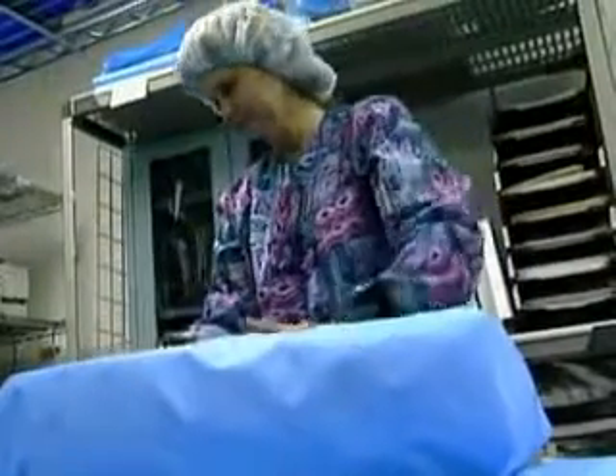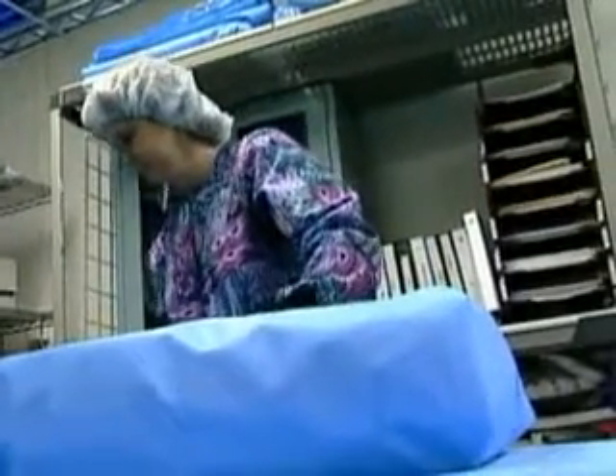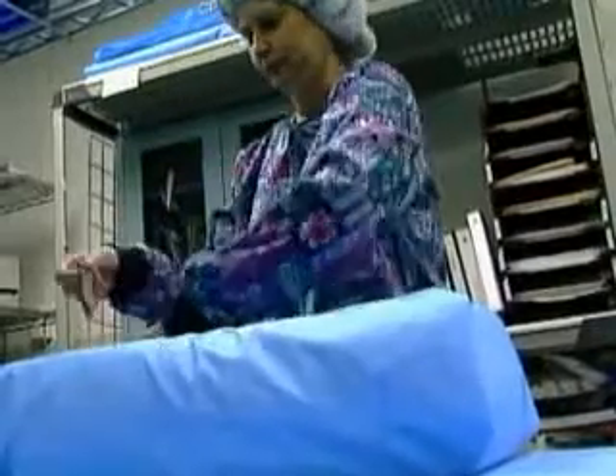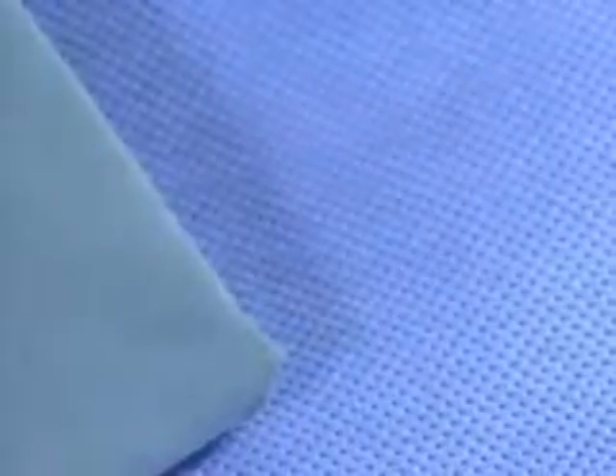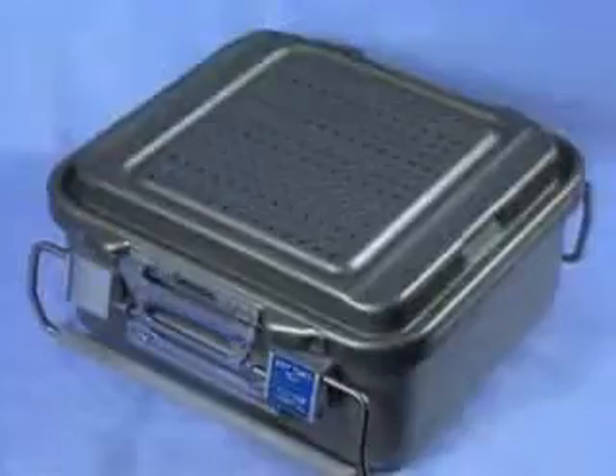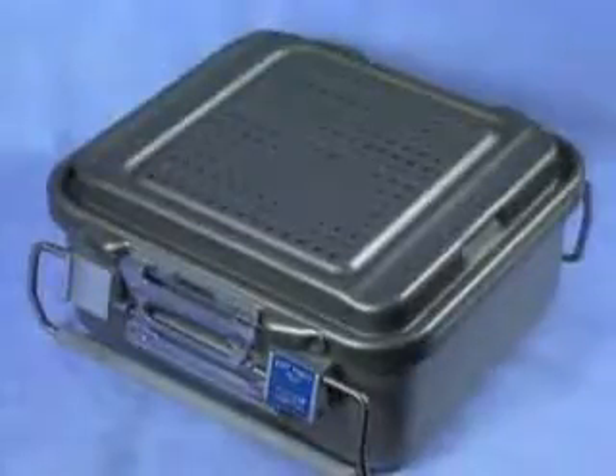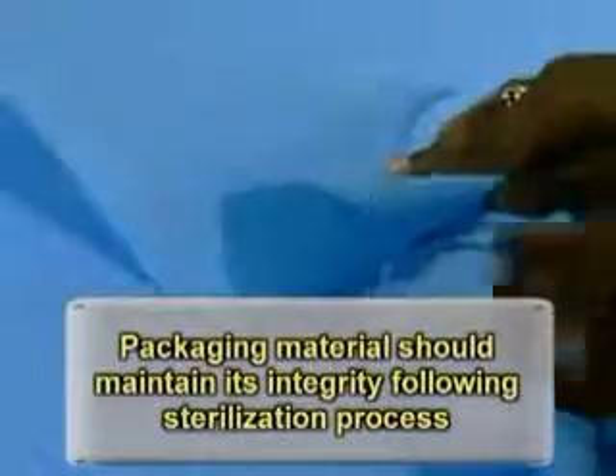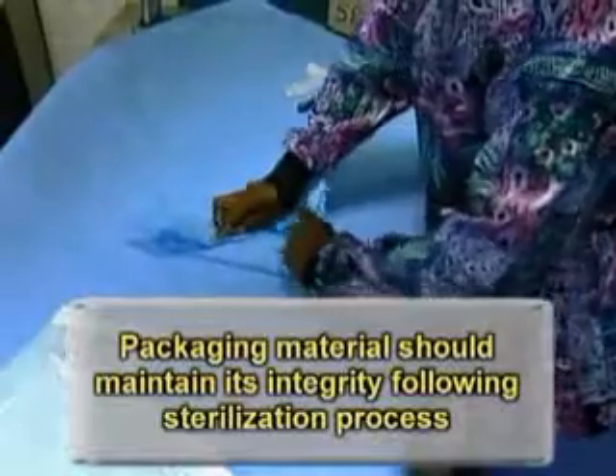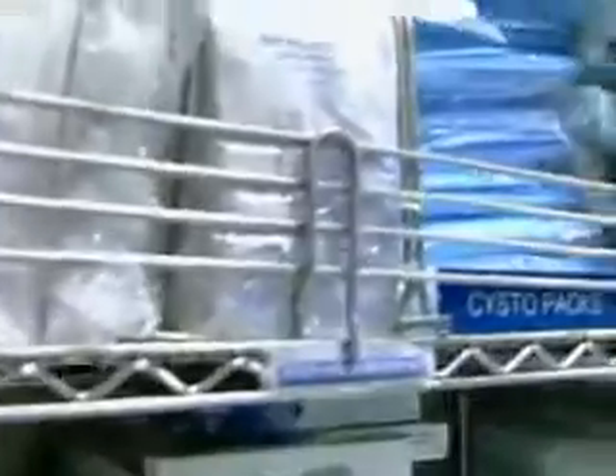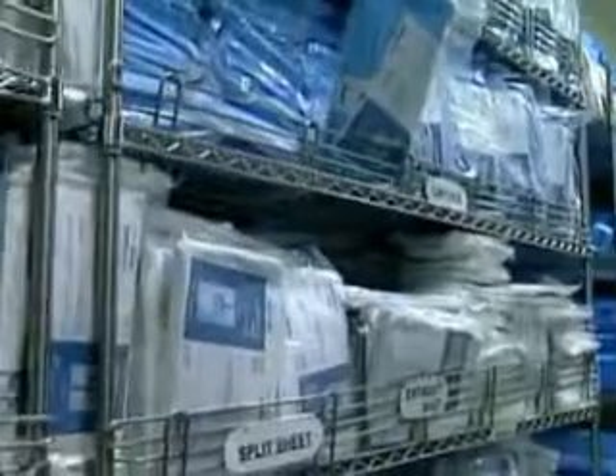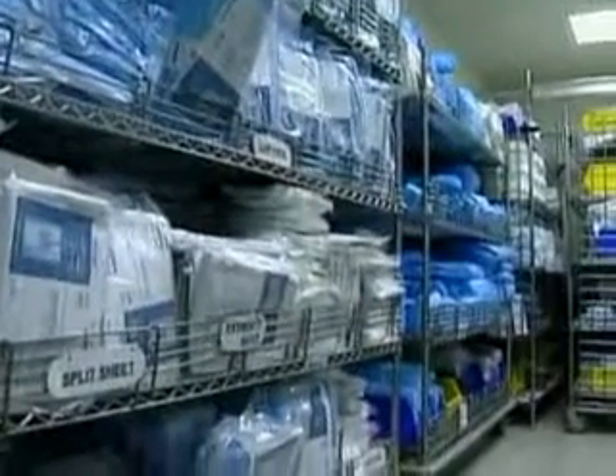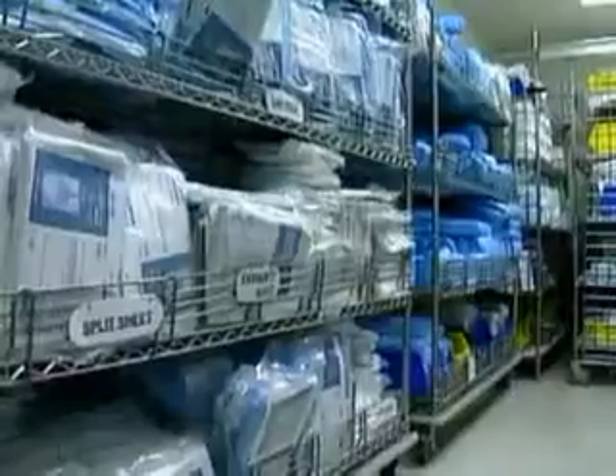The next step is preparing items for packaging. Packaging materials must be compatible with the sterilization process. Packaging materials may be woven or non-woven material, peel packs of plastic and/or paper, or rigid container systems. If the sterility of an item is to be considered event-related, the packaging material should be strong enough to maintain its integrity following the sterilization process and protect the item from contamination. Plastic dust covers also can be used to further protect contents.